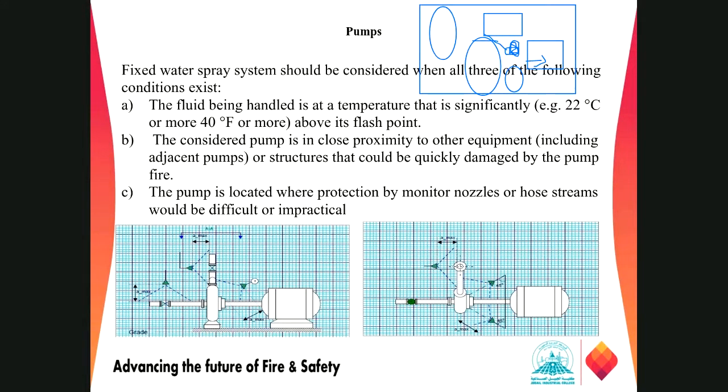Now, if you can see the location of the spray nozzles, we have one nozzle at this one, in between the motor and the impeller. One at the gate valve outside, the valve after the discharge line, and then one at the suction side and the discharge side, right? This is the sectional view, and this is the top view. The same drawing.